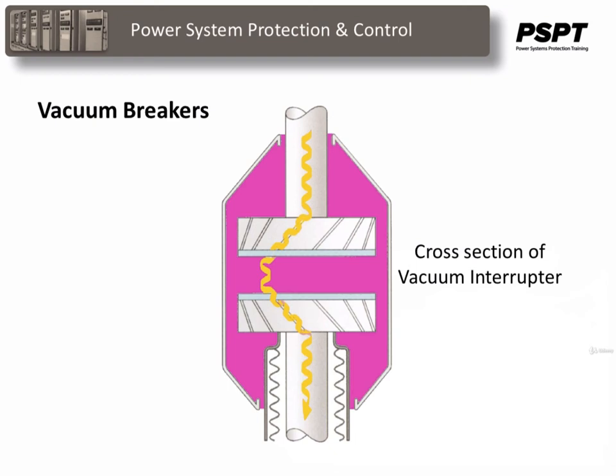When two face-to-face contact areas are just being separated from each other, they do not separate instantly. Contact area on the contact face is being reduced and ultimately comes to a point when they are finally detached. All of this happens, of course, in a fraction of a microsecond. At this instant of detaching the contacts in a vacuum, the current through the contacts concentrates on that last contact point on the contact surface, and makes it a hot spot. As it is in a vacuum, the metal on the contact surface is easily vaporized due to the hot spot and creates a conducting medium for an arc path. Then the arc will be initiated and continue until the next current zero.